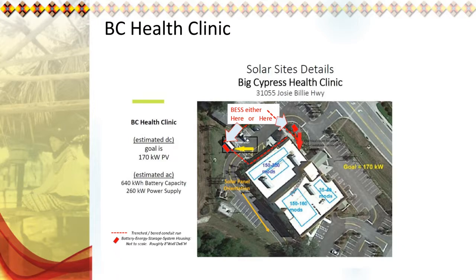For the Big Cypress Medical Clinic, it looked like we could have done carport-mounted panels on this parking lot as well. However, there are exfiltration trenches under that parking lot which would probably be affected or compromised by carport-mounted solar panels, so we looked at other options. The roof is fairly new and in good shape, and after analysis we expect that placing solar panels on the roof should generate about 170 kilowatts of photovoltaic energy. If that's not enough, we can use the parking strip to the southwest of the building. We expect to hook this facility up to a 640 kilowatt hour battery backup, again right next to the generator.